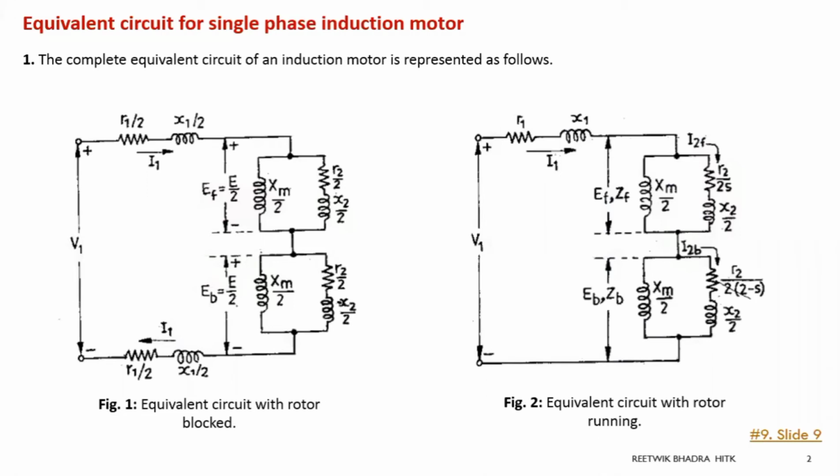What we had done last day is that we had seen that if I give a single phase supply, there was no rotating magnetic field created. So we have to split that single supply into two parts, so that a resultant was produced and that resultant would be rotating in nature. So that's why we were using two windings: one was a main winding and one an auxiliary winding.